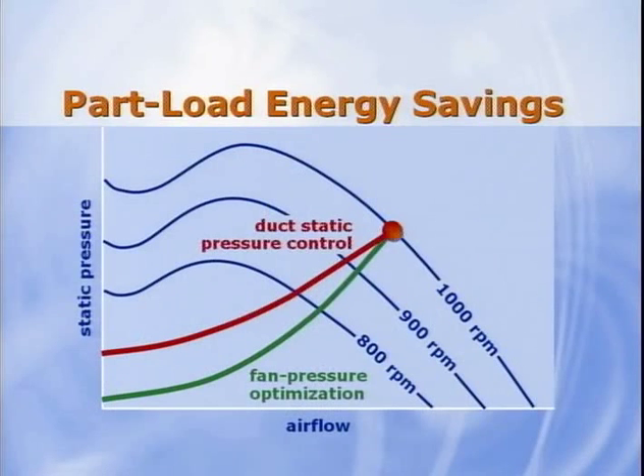This concept, which we call fan pressure optimization, has several benefits. First is that it reduces supply fan energy use. At part load conditions, fan pressure optimization allows the supply fan to operate at a lower static pressure and therefore use less energy. Second, lowering duct static lowers sound levels. Because the supply fan doesn't need to generate as much static pressure, it typically generates less noise. And with lower pressures in the supply ductwork, the dampers in the VAV boxes will be more open, resulting in less noise generated at the boxes.